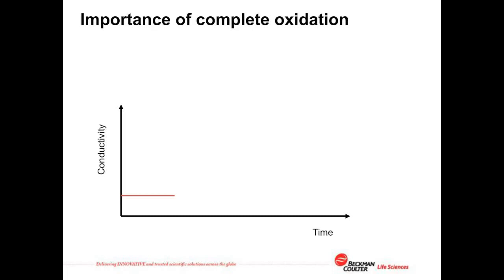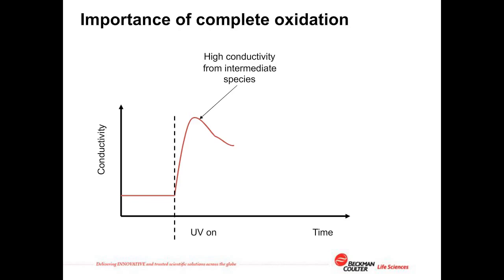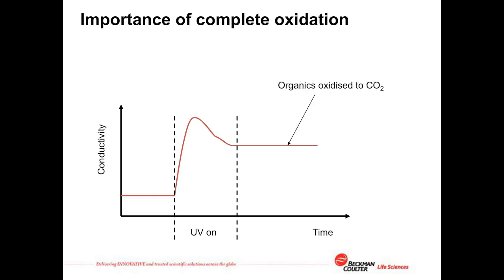Most TOC analyzers used to monitor pharmaceutical grade water use ultraviolet light to oxidize the organic materials, releasing the carbon atoms in the form of carbon dioxide. Carbon dioxide dissolves into the water, elevating the conductivity, and it's this change in conductivity that is measured by the TOC analyzer and used to calculate the amount of organic carbon present in the water.